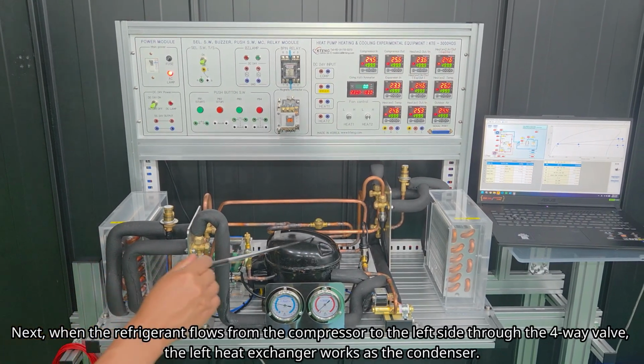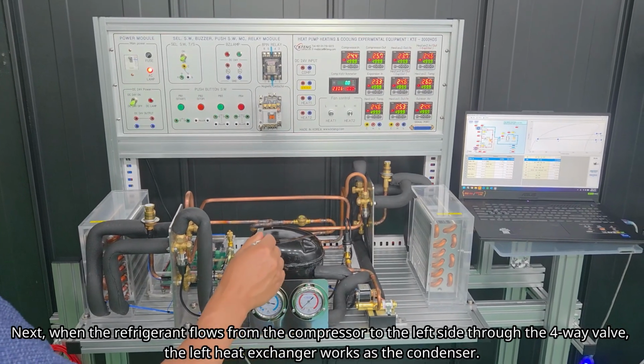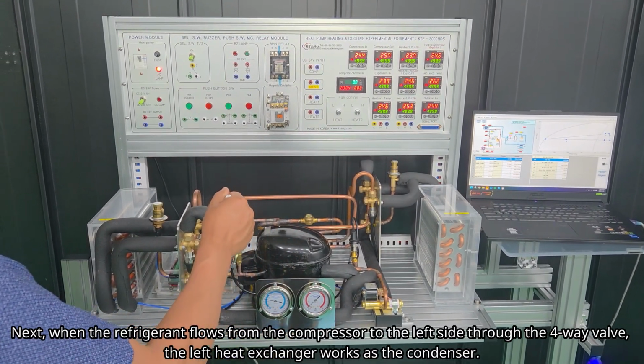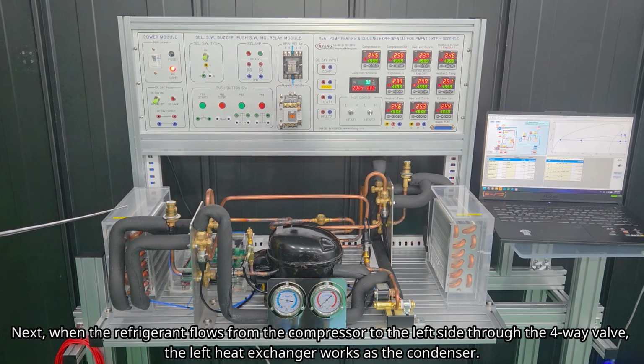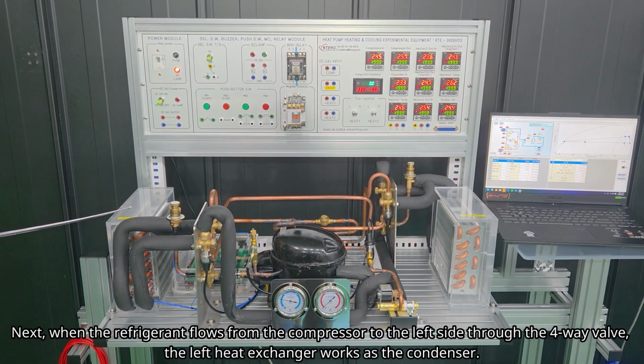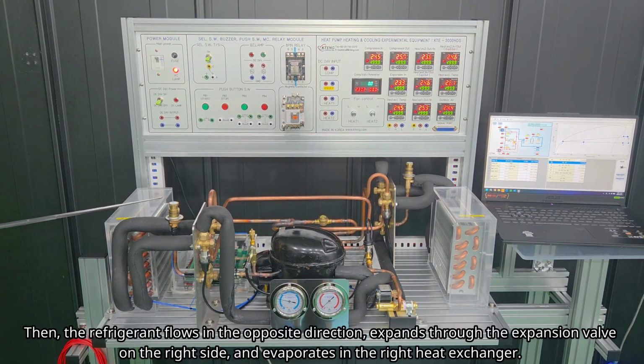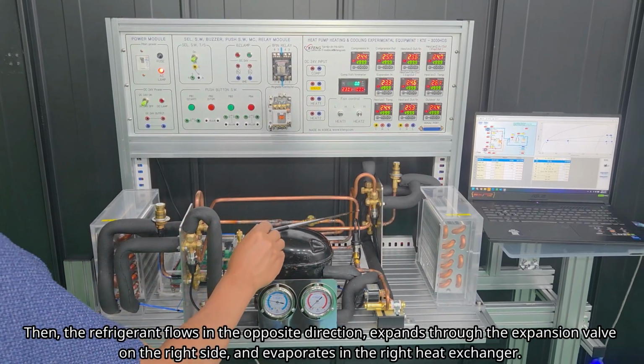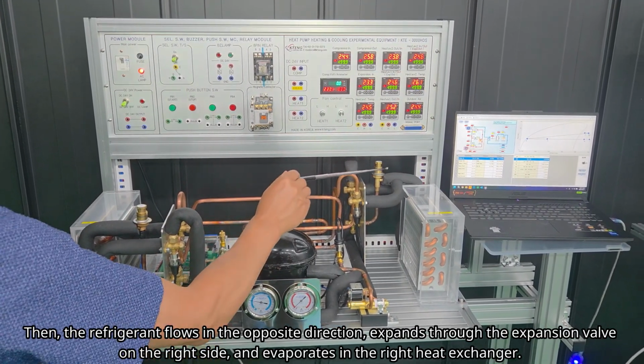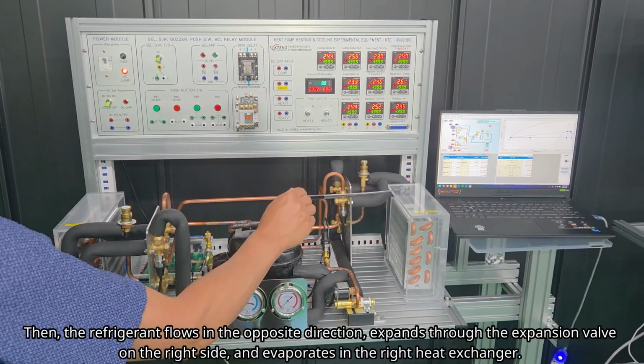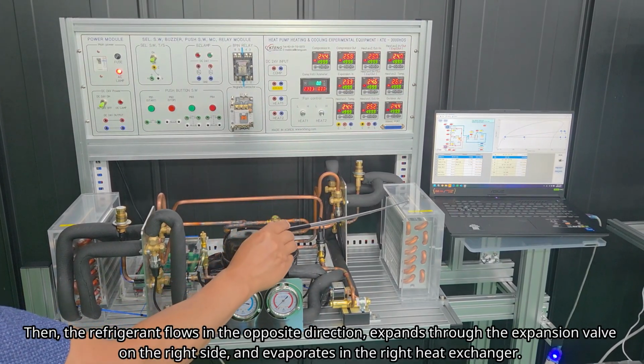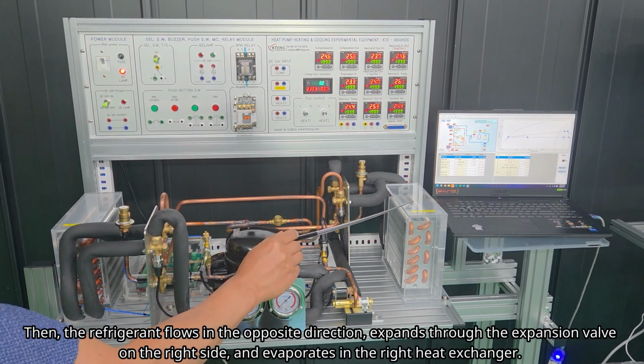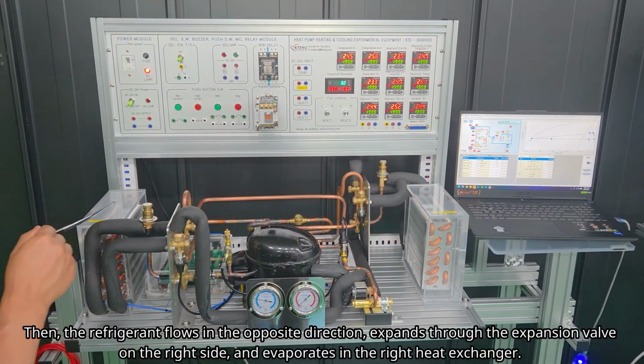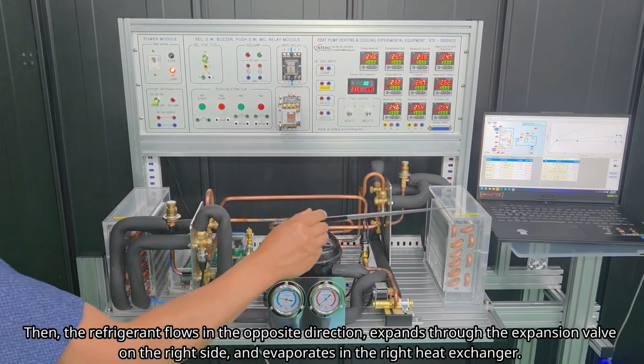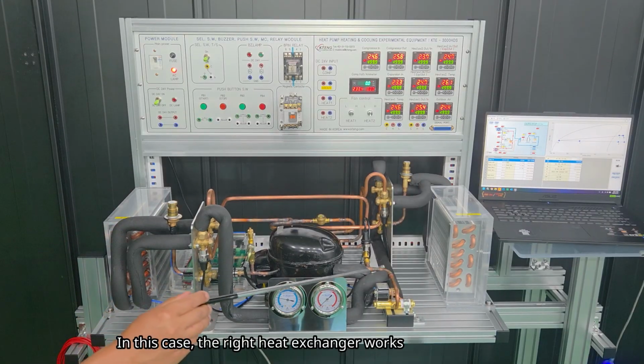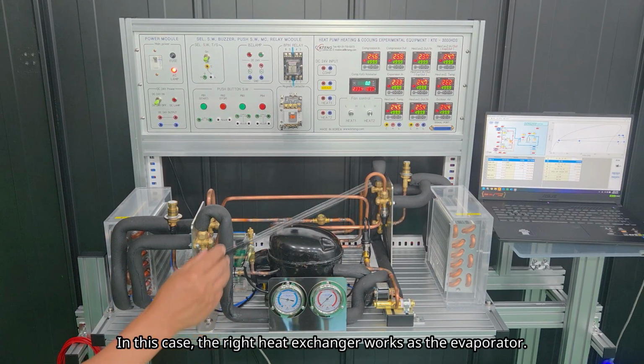Next, when the refrigerant flows from the compressor to the left side through the four-way valve, the left heat exchanger works as a condenser. Then the refrigerant flowing in the opposite direction expands through the expansion valve on the right side and evaporates in the right heat exchanger. In this case, the right heat exchanger works as the evaporator.